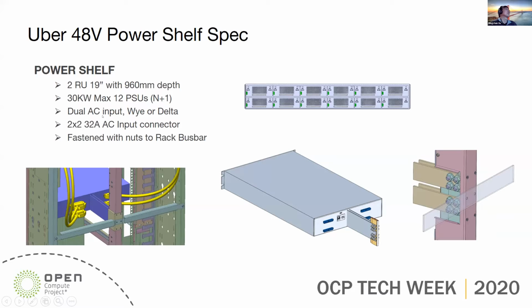Just now I mentioned we have the dual AC source. The power shelf can work with either Y or delta connections from the grid source. Also, please note there are 2 AC connectors from each source to the power shelf. That gives flexibility, so the power shelf can work with either the higher amperage AC plug from the busway, or 2 smaller amperage AC plugs from the busway.